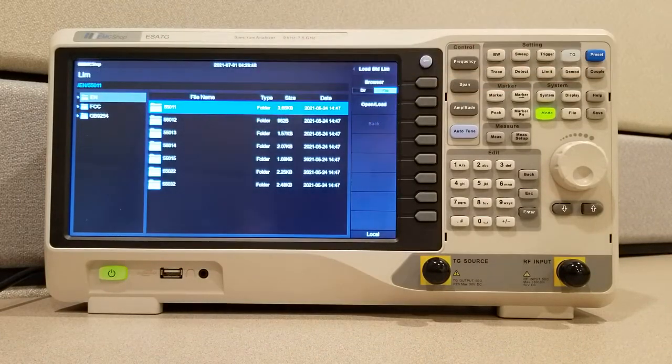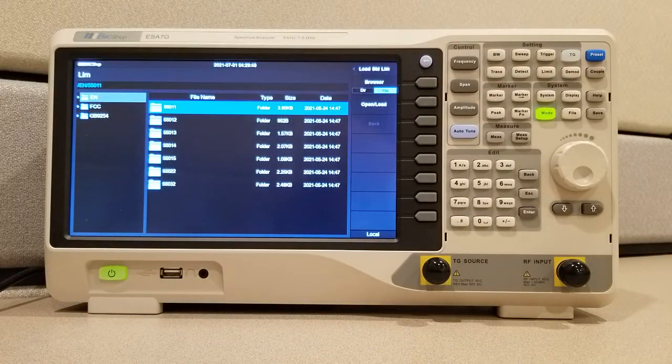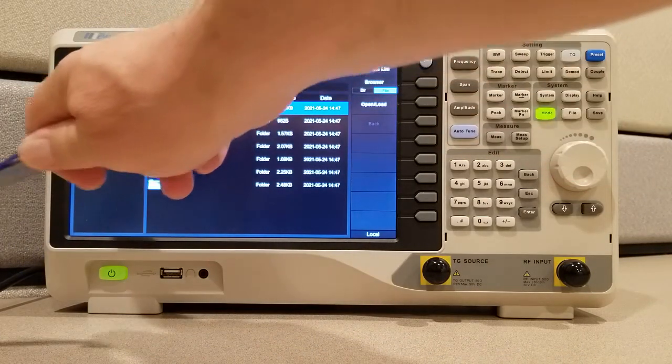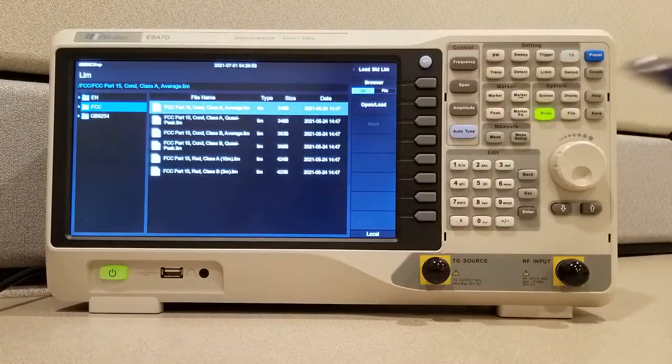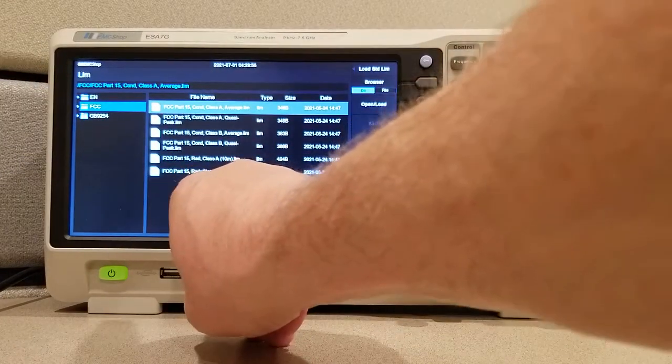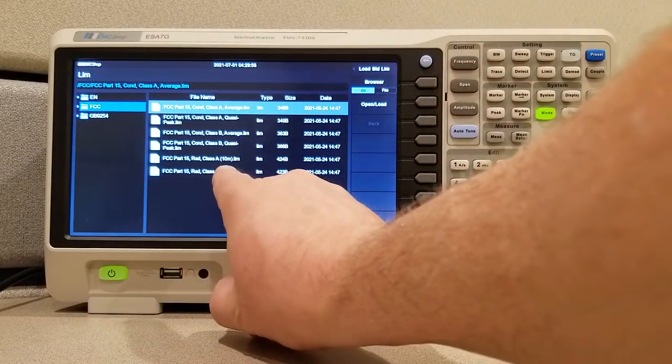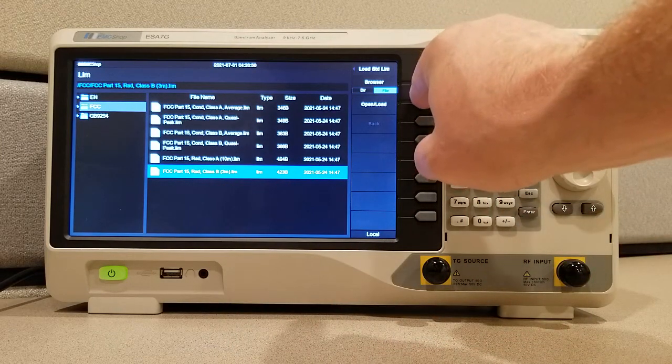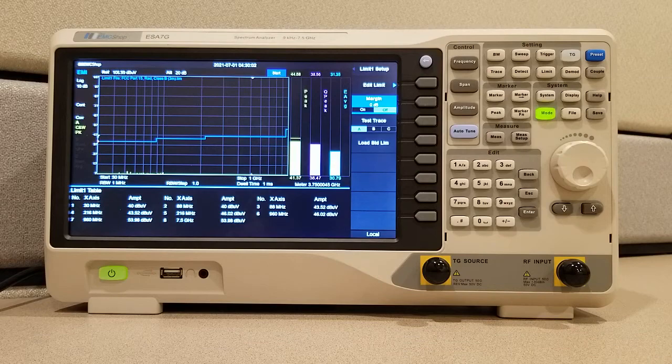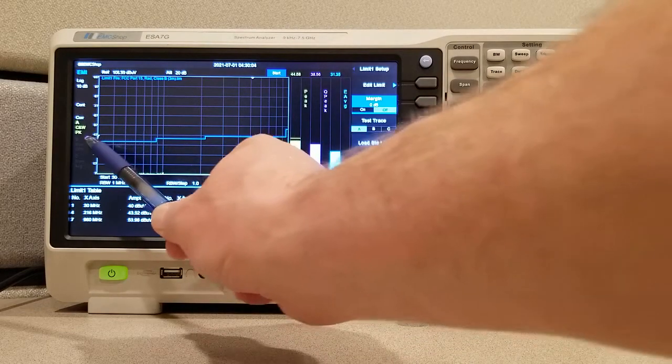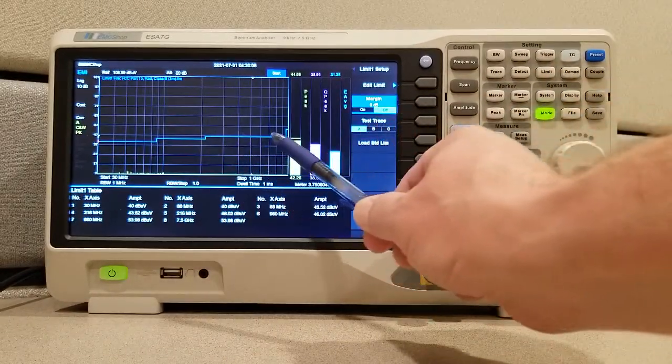And in this case, you'll be able to see three folders with preloaded limits in it. And we're going to choose the FCC. Go to FCC part 15 radiated class B at 3 meters. And load that file in. And you'll see the limit automatically gets put in there.